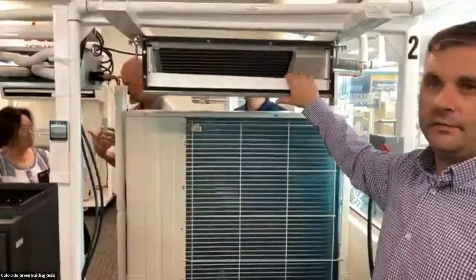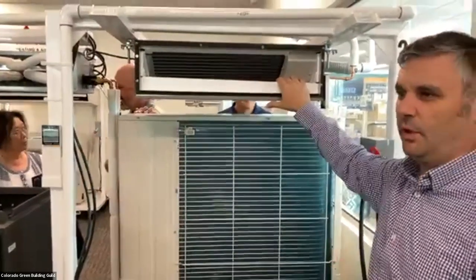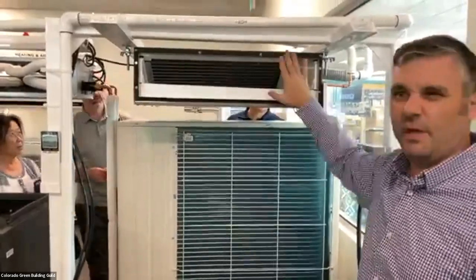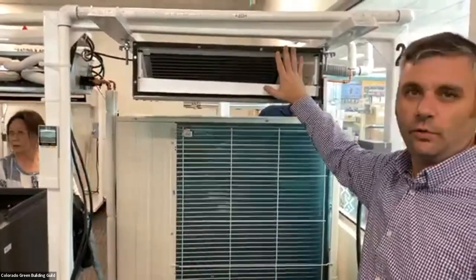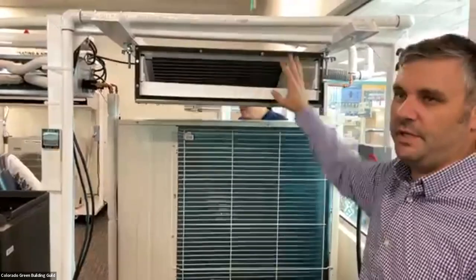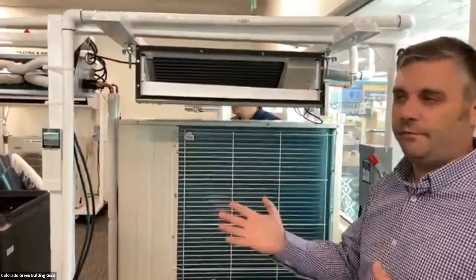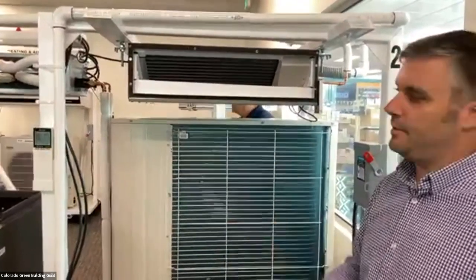The PEAD gives us a little bit more static pressure, so we can make longer duct runs. With something like this, we've maybe got about 10 to 15 feet total of duct we can use. With the PEAD, we're probably going to get up to 30 to 50 feet of duct we can use.